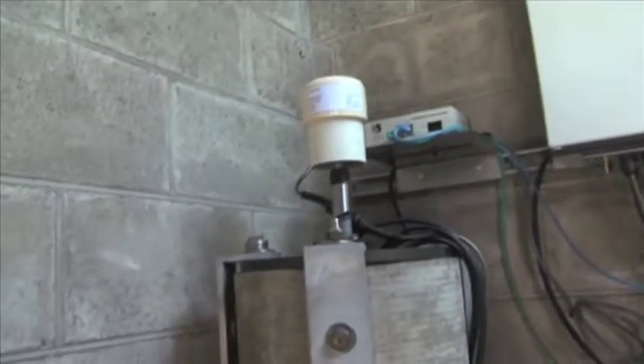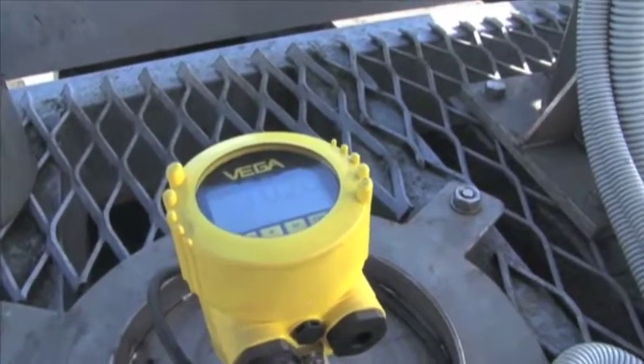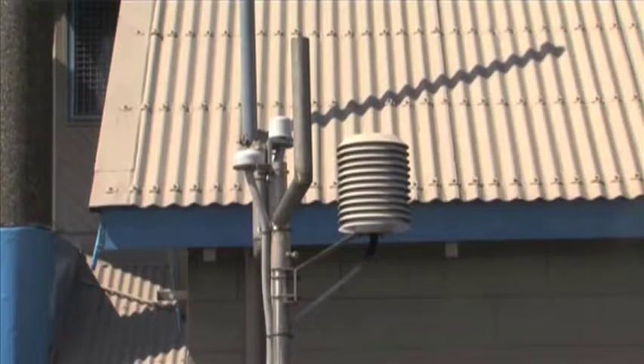We've got the primary sensor being the aquatrack, and the secondary is the vega sensor, and the tertiary is the pressure sensor, the vega being a radar sensor. We also have meteorological data with temperatures of in-water temperature, air temperature in a beehive screen, wind speed and direction, and a barometer.